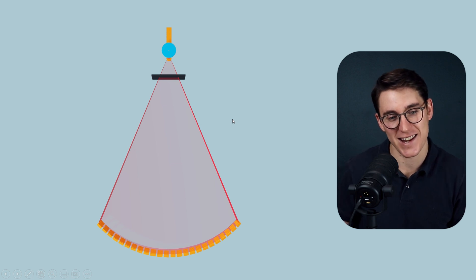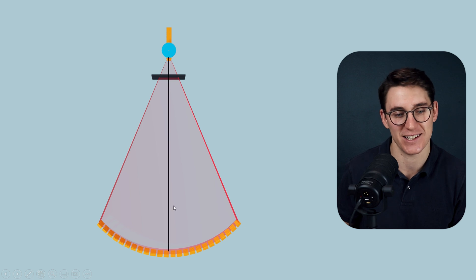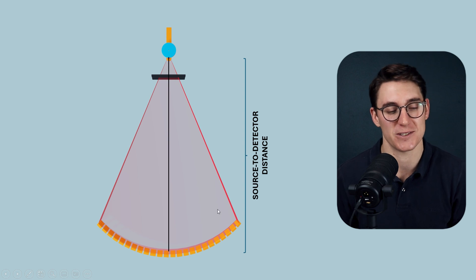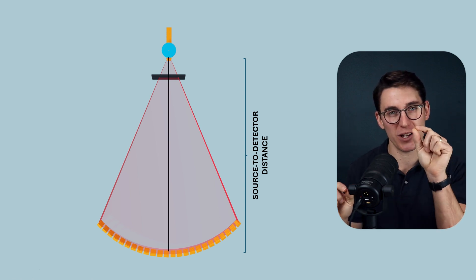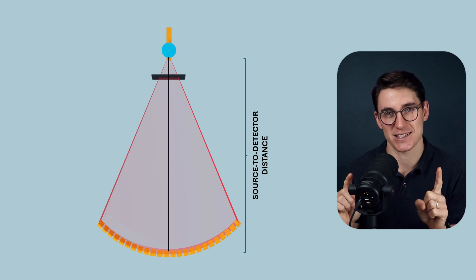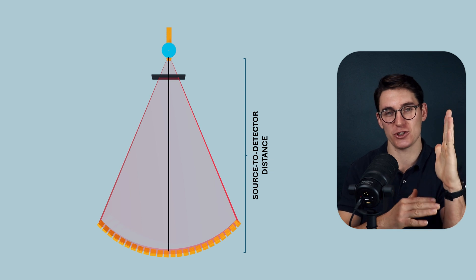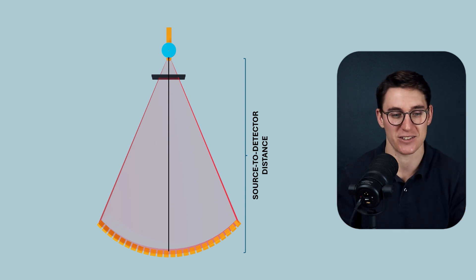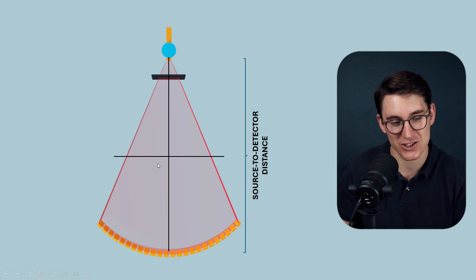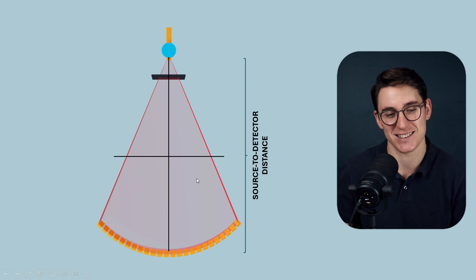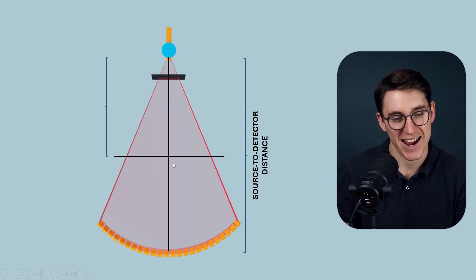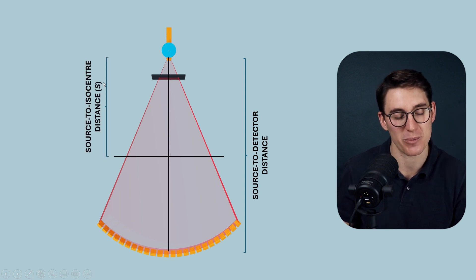We can draw a line connecting the anode directly to the detectors that bisects the fan angle — down the middle of our beam. This is what's known as the source to detector distance, and we can actually calculate this distance. When a third generation CT scanner rotates, there is a point that is the center of that rotational axis — that point doesn't move. Generally in a 512 by 512 pixel array, that point is the isocenter, representing the pixel at 256 by 256 in the x-y coordinates. The distance from the source to the isocenter can be represented by the letter S.